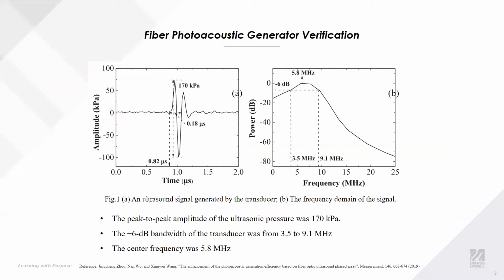So this figure shows the experiment results. Figure A, on the left, shows the time domain of the generated acoustic signal. You can see that the peak-to-peak amplitude of the ultrasound pressure was 170 kilopascal. And figure B is the FFT of the time domain signal. This frequency plot shows that the center frequency was 5.8 megahertz, and the 6 dB bandwidth of the transducer was from 3.5 to 9.1 megahertz.